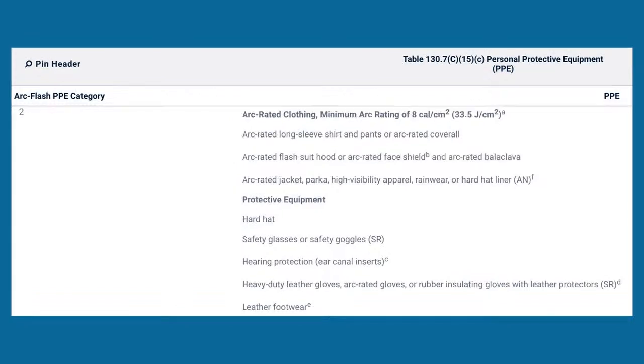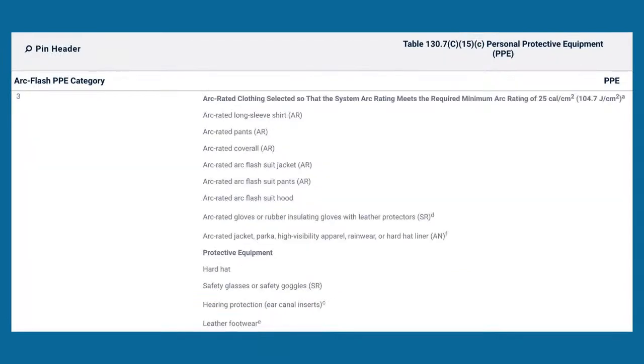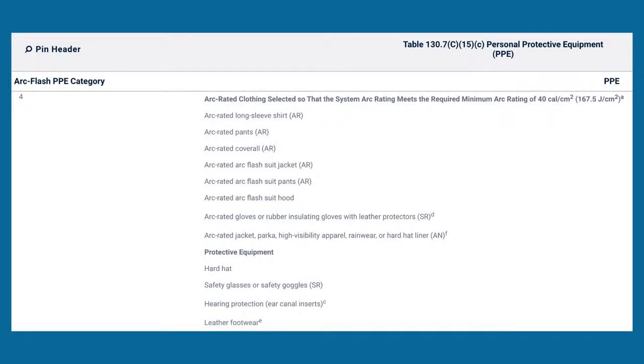Now, once I get up to hazard risk category 2, this is up to 8 cal. And you're going to see an arc flash suit hood or arc rated face shield and arc rated balaclava. And then you go down, you do your selection. Then I go up to 8 to 25 cal for a hazard risk category 3. And look, you just start seeing it change. They start wanting more stuff on to protect yourself. And then, of course, the last one is hazard risk category 4, which goes up to 40 cal.